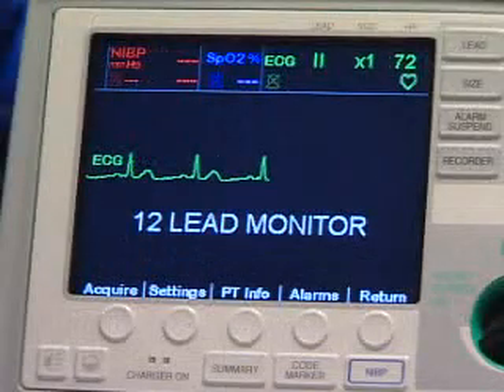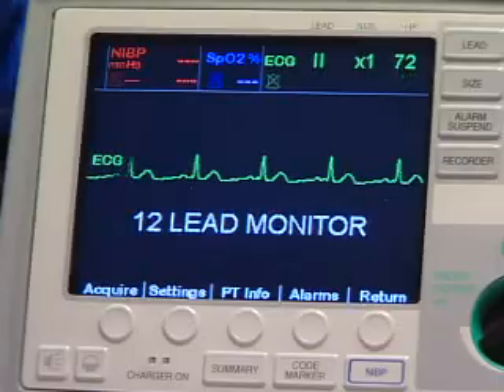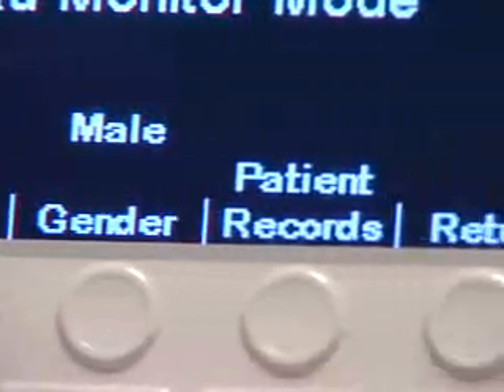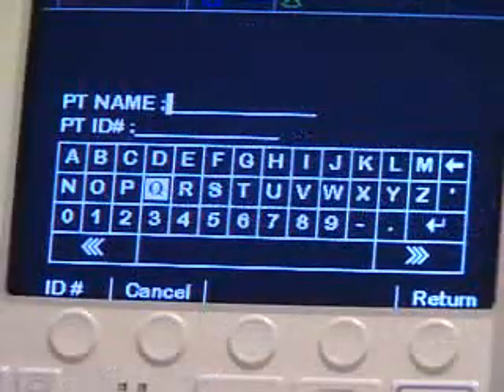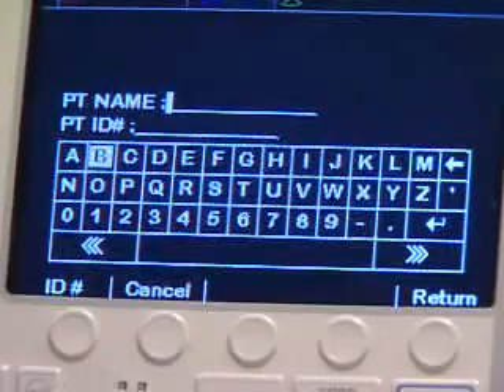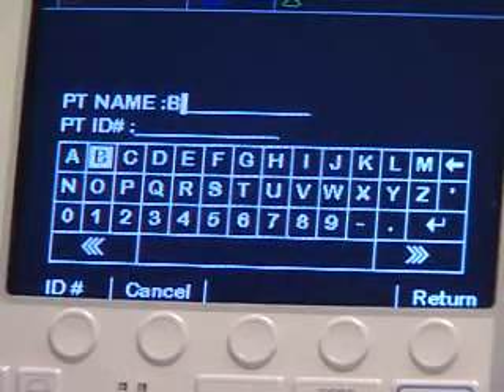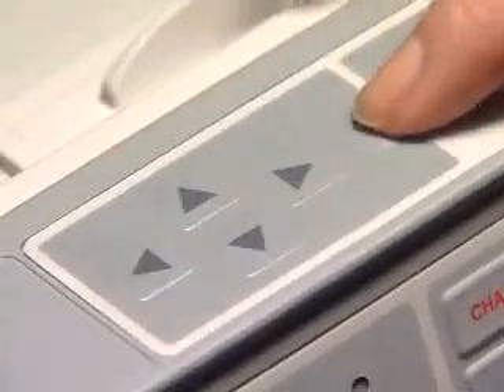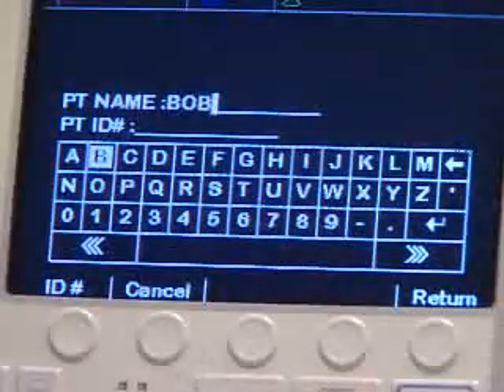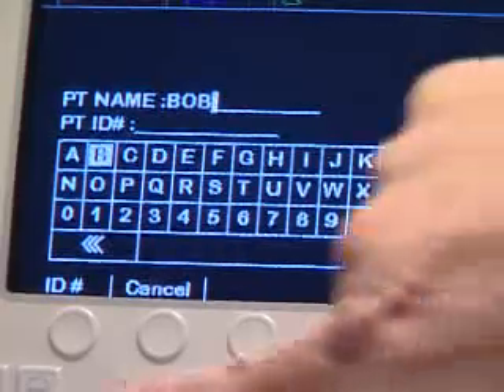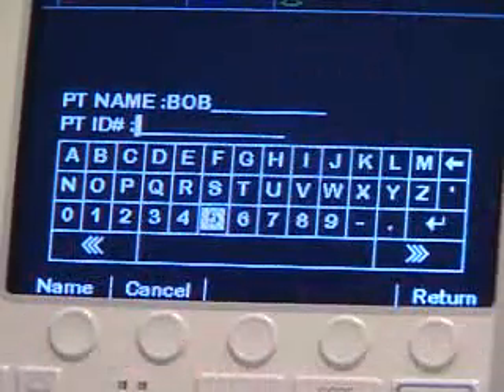Pressing the Patient Info soft keys allows access to the patient demographic information. You can select from ID number, age, gender, patient record, or return. Press the ID number soft key to access the name and the ID number screen. The cursor goes directly to the patient name field. Use the scroll keys on top of the E-Series to select a character on the keypad, and then press the Commit key to enter. When you have entered the patient name, select the Patient ID number soft key.